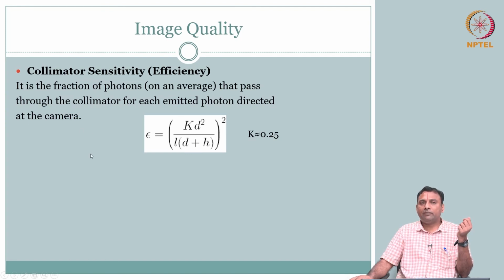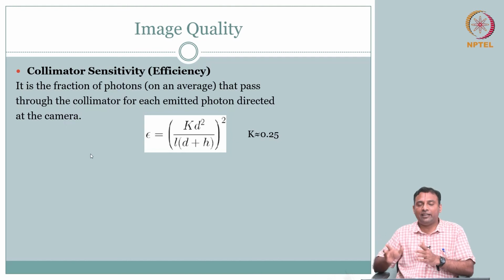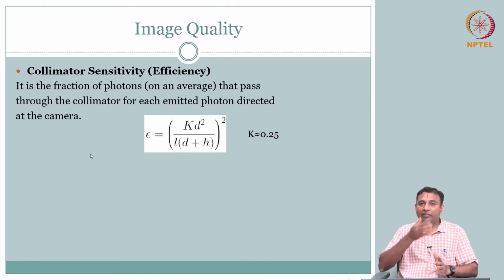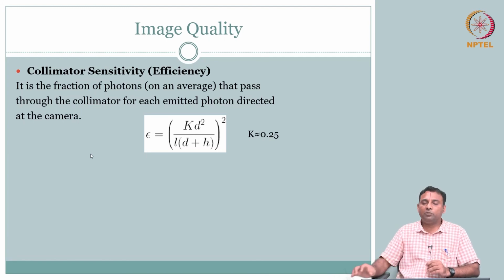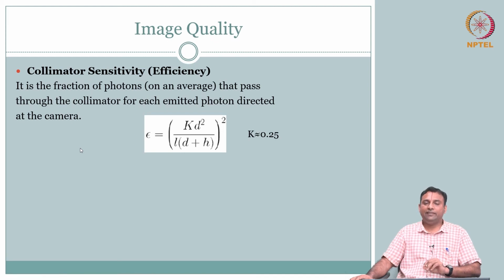So in some sense, when you do the radioactive tracer, when you engineer that radioactive tracer, you have an energy band, and then you engineer the detector side, the Anger camera side, you make everything as close to the best case scenario for that particular energy, right. So it is not like one detector fits all.